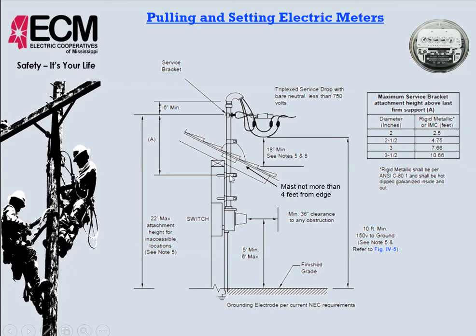So where is the last place this conduit is strapped to the wall? It's connected to the meter base right here, and then would periodically need to be attached to the wall as well to support this weight and this pull of our service entrance, our service coming into and attaching to the pipe. So 2 inches is probably what we're going to see, so no more than 2.5 feet between these two. So it would need at least one strap, and it can't be any more than 2.5 feet.